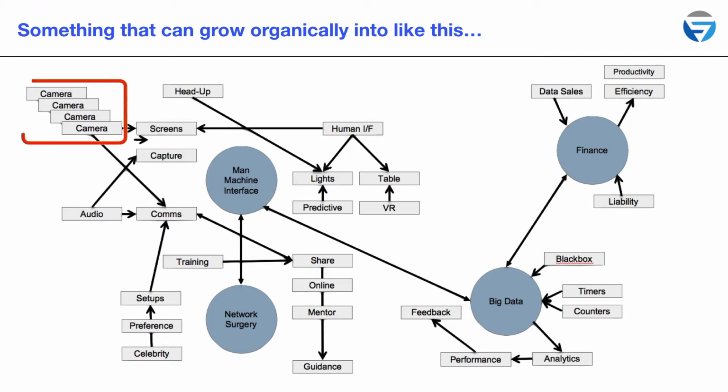So this is where we are now, pretty much. You have a number of video sources: camera, C-arm, ultrasound, endoscope. That's the normal. The camera could be the in-light camera, room camera. And then you have a number of displays, two surgical displays, maybe a big flat panel on the wall. And you have a human interface, normally a video touch panel. So you just press a few buttons and you do your routing. And that's controlled by a machine, which is called your man-machine interface controller and the routing controller. And that's every system for the last 20-odd years, pretty much.